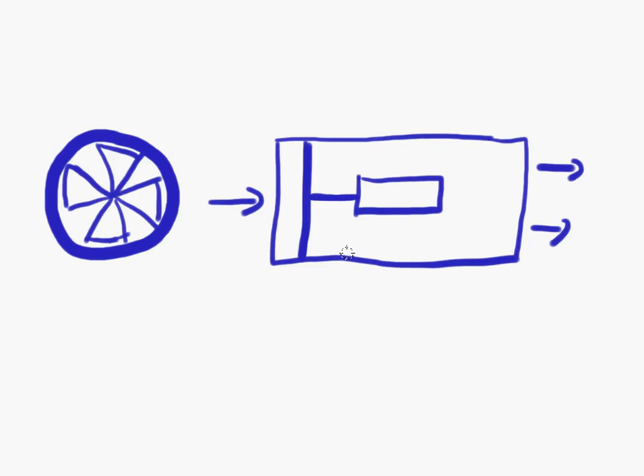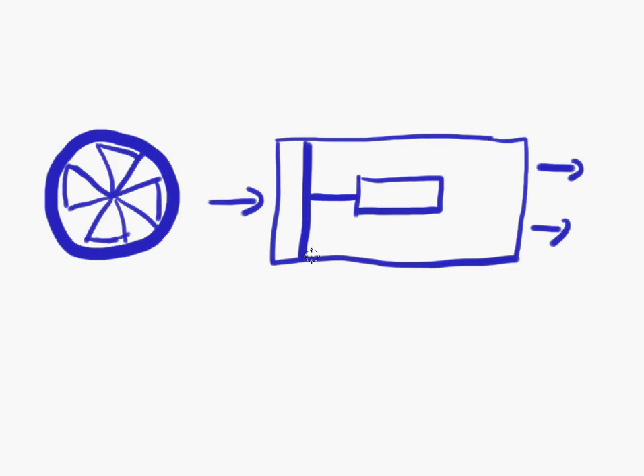Now in a bifurcated fan, the objective is the following: sometimes you have dirty air, let's say air filled with dust you'd find in woodworking factories or similar environments. Sometimes you have extremely hot air or air filled up with some chemicals or stuff like that.